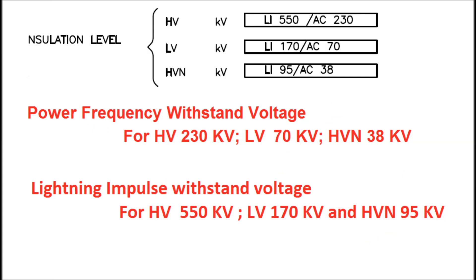The next parameter in the nameplate is the insulation level of the HV side, LV side, and HV neutral. There are two types of insulation: power frequency withstand voltage and lightning impulse withstand voltage. For the HV side, the power frequency withstand voltage is 230 kV; for the LV side it is 70 kV; and for the HV neutral it is 38 kV.